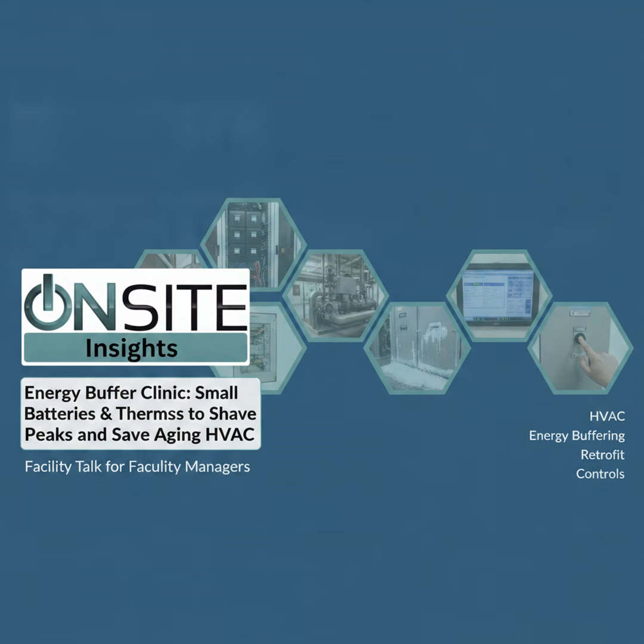Tiny and glorious, exactly. The pilot cost less than a single emergency visit. Scoped, documented pilots de-risk decisions and make you tougher to oversell. 3 things to do this week. 1. Pick a single trouble RTU and run 24 hours of baseline logging. 2. Call your electrician and discuss a control side UPS. Use the 4 vendor questions Blaze gave you. 3. Scope a 1-day pilot and commit to logging results for 2 weeks.